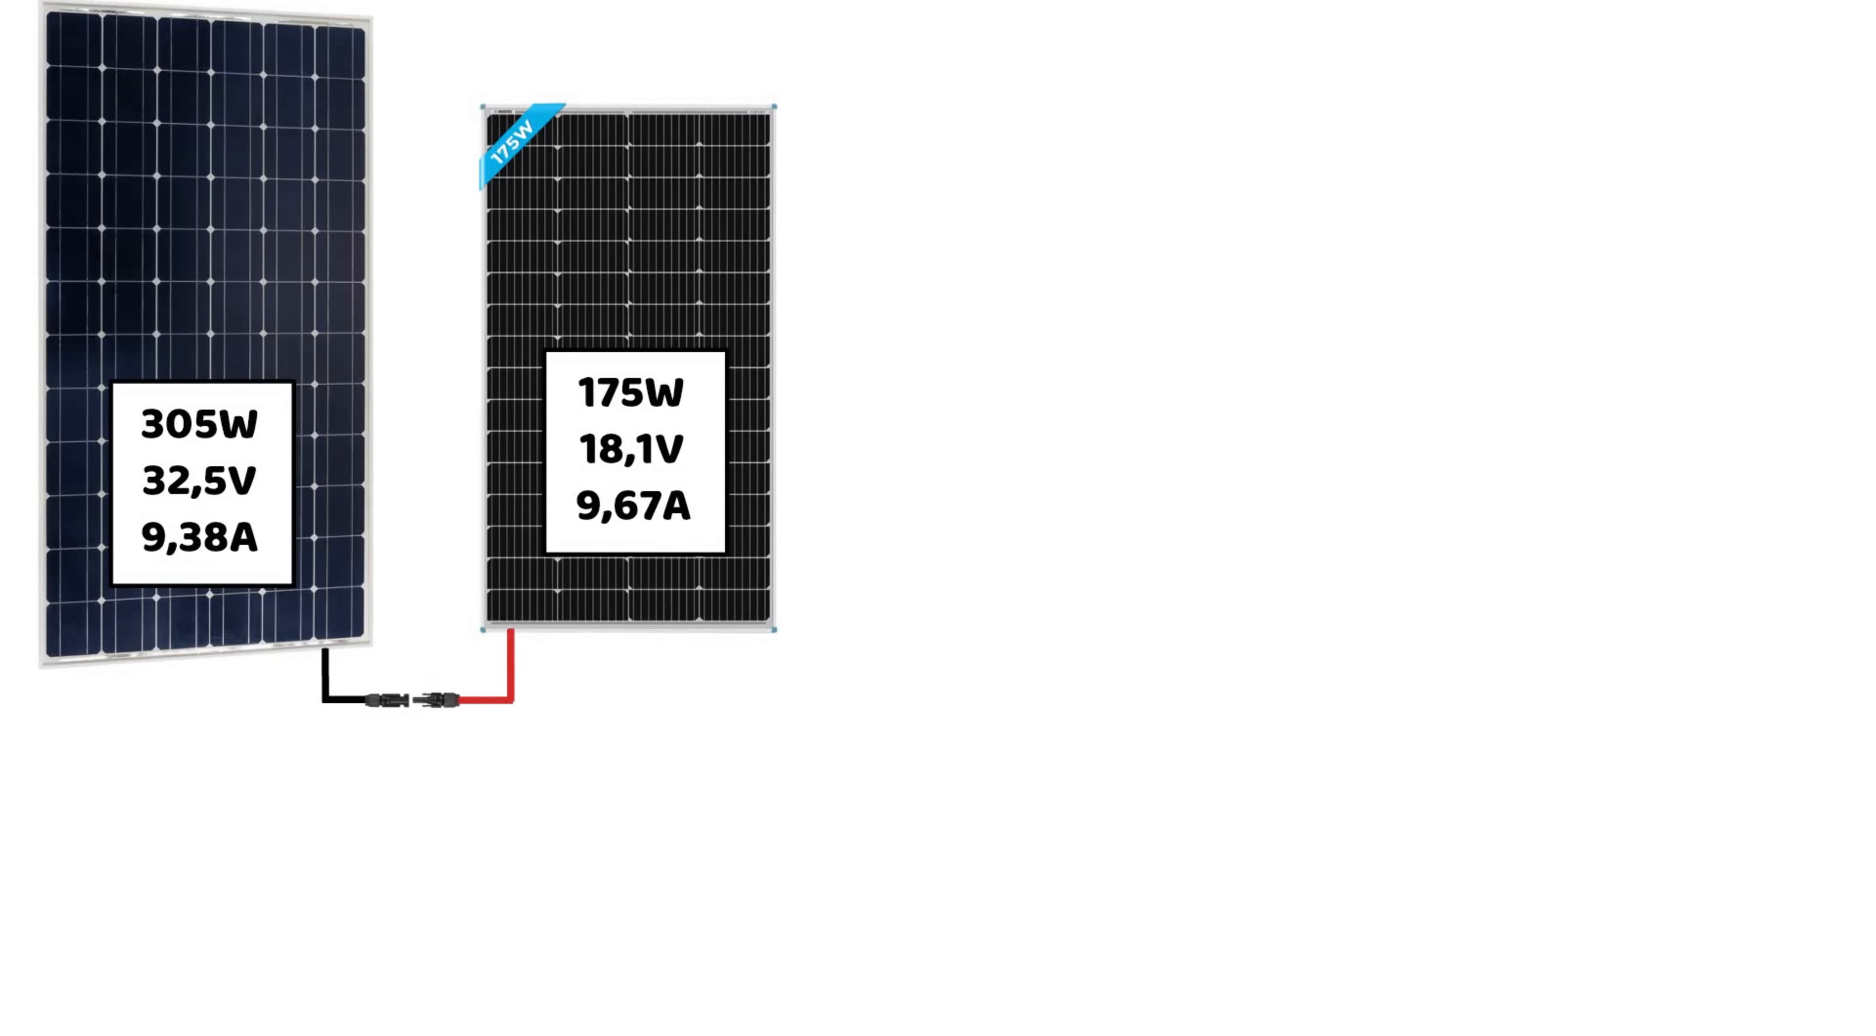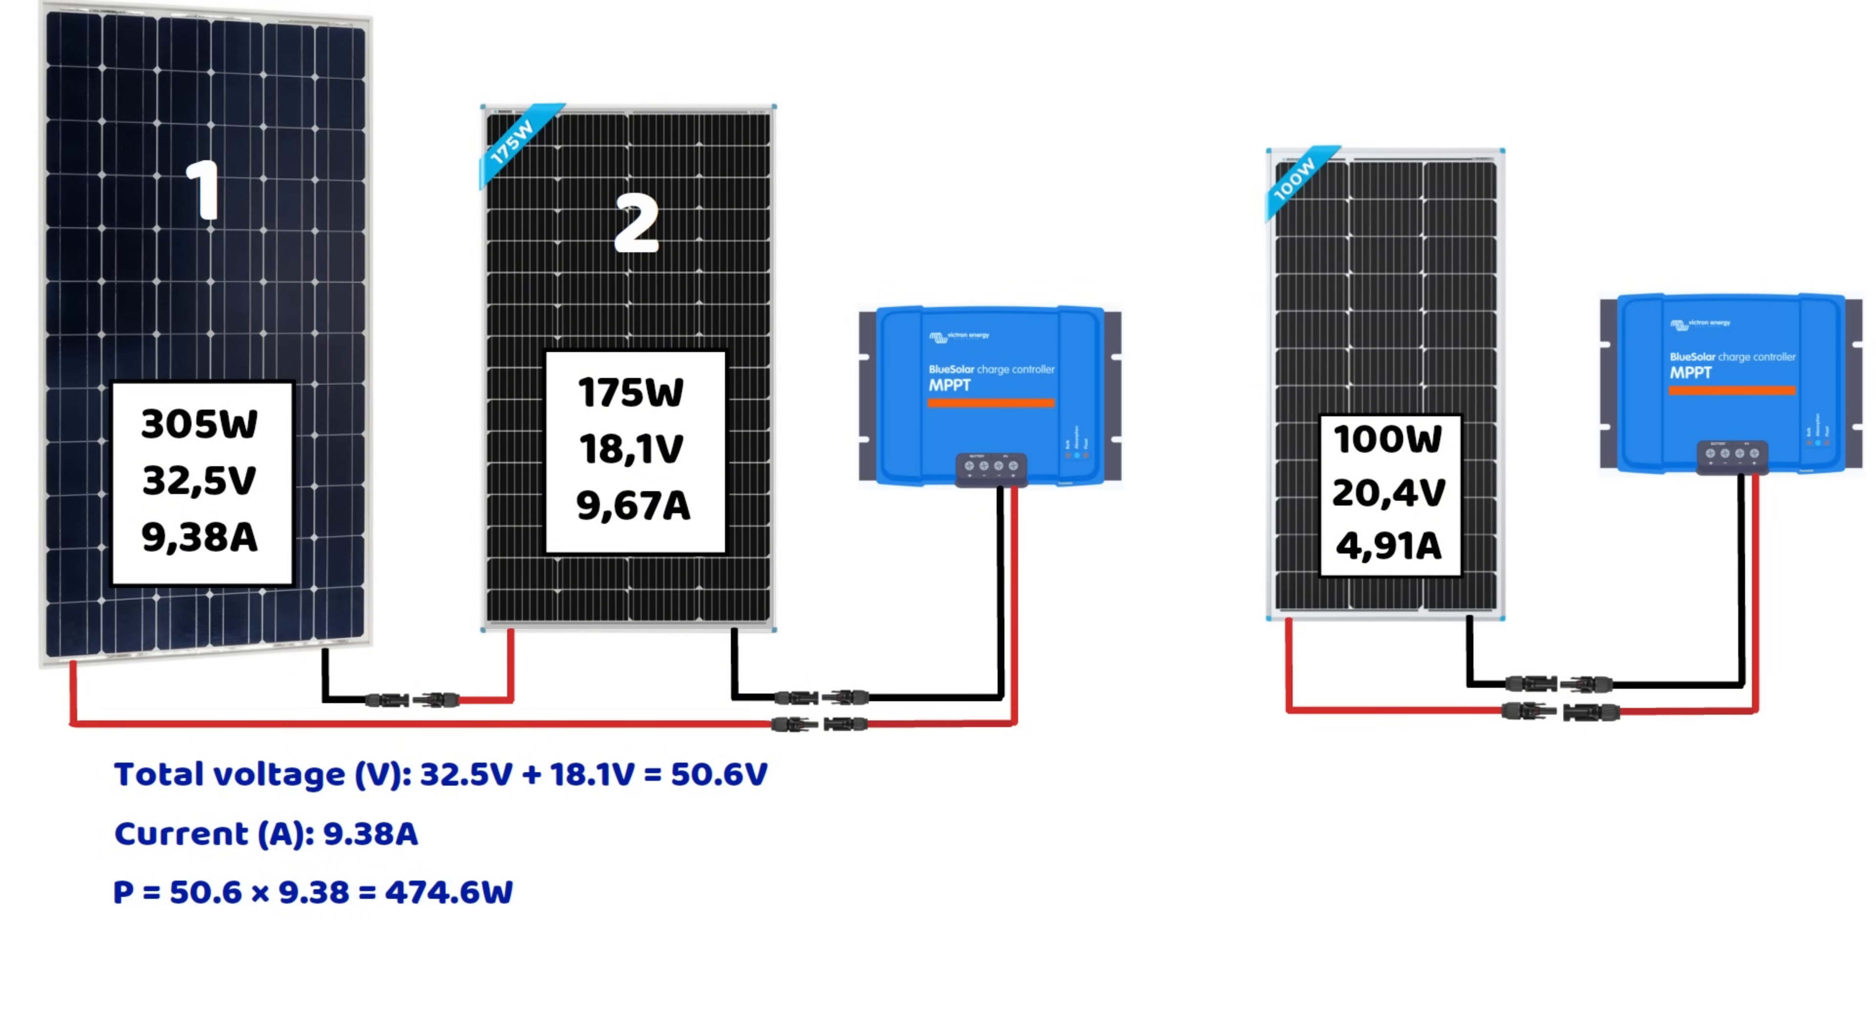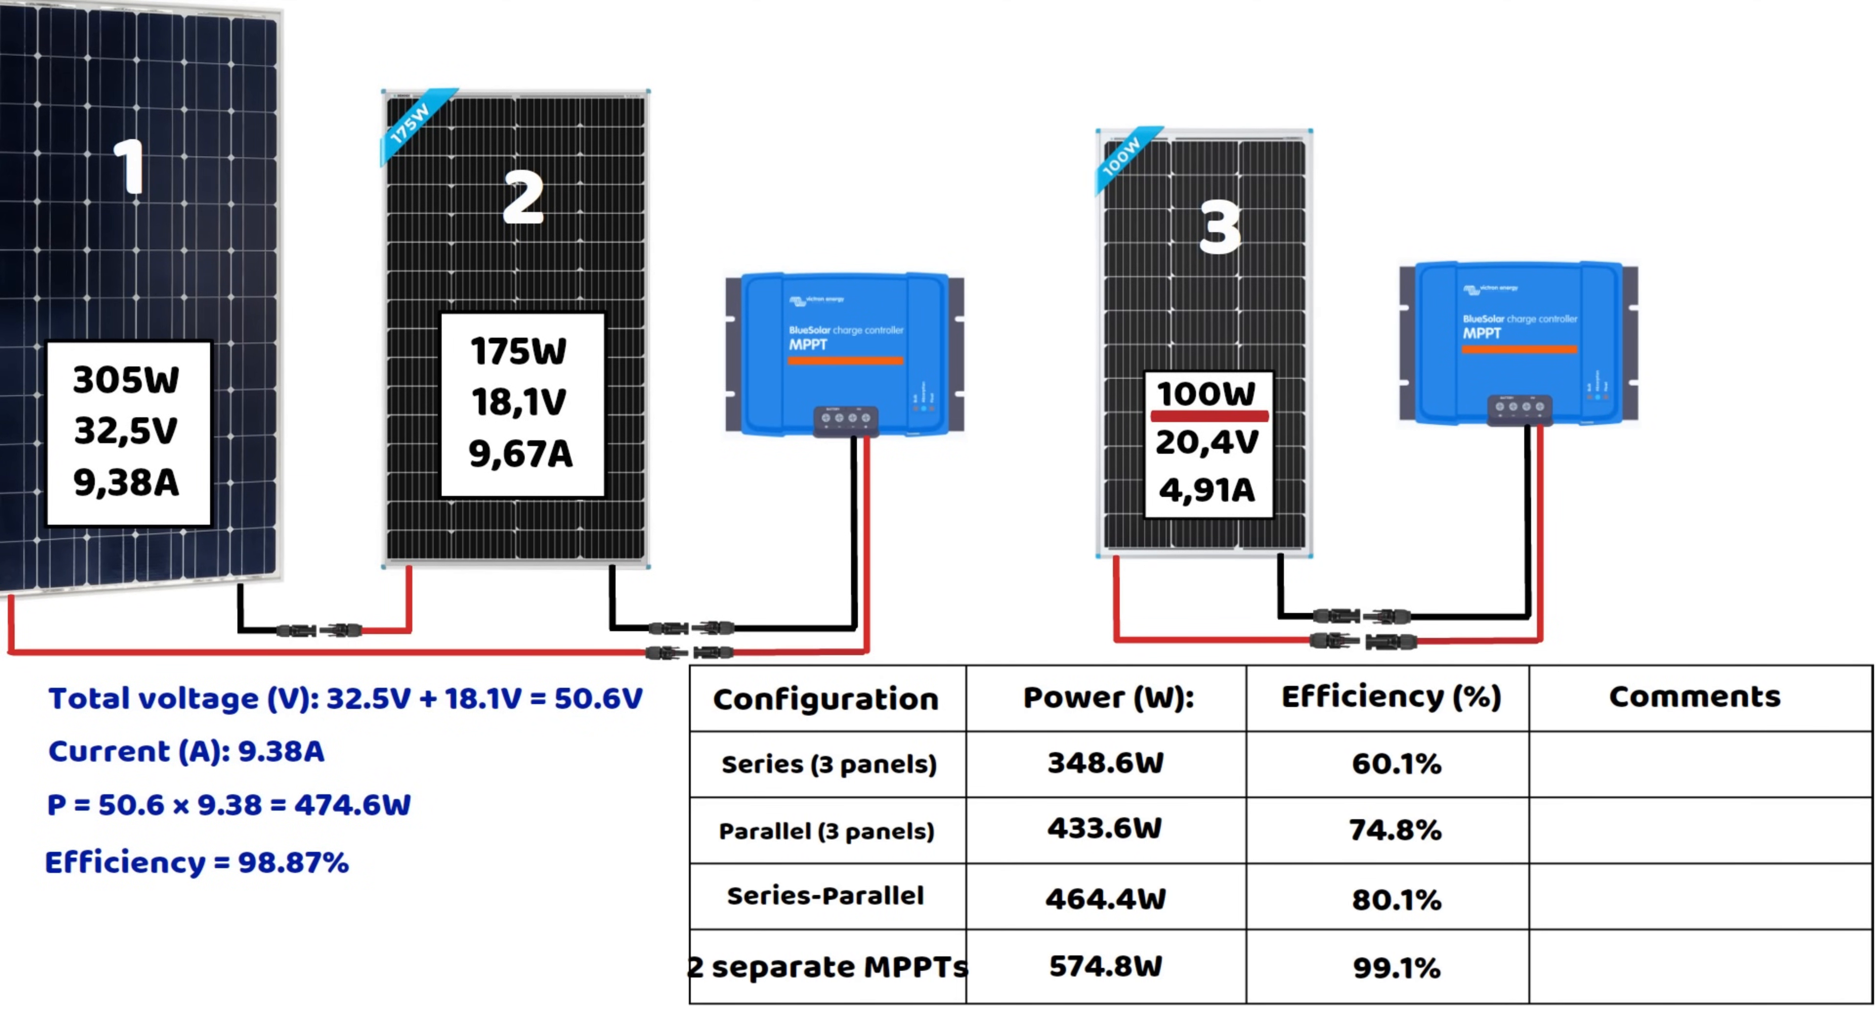For this type of scenario, using two separate MPPT controllers is often the best solution when dealing with panels that have very different specifications. Here's a better configuration, again with two groups. An MPPT controller connected to panels 1 and 2 in series. This gives us a total voltage of 50.6 volts, a current of 9.38 amps, and a total power of 474.6 watts, which corresponds to an efficiency of 98.87%, virtually no loss. An MPPT controller connected exclusively to panel 3. Here, it will deliver its 100 watts. No loss, thus optimal efficiency. In this table, you can see a summary of all the connection variants we've tried and the most efficient one.